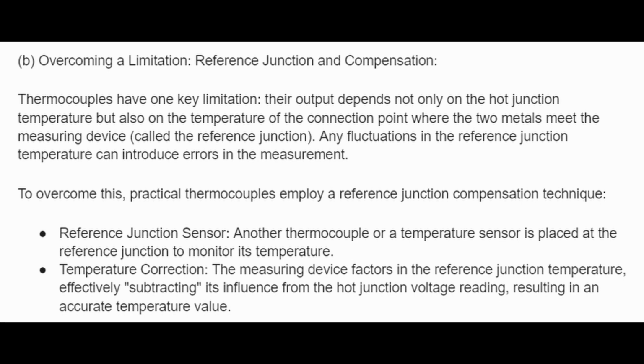Reference junction sensor. Another thermocouple or temperature sensor is placed at the reference junction for temperature correction. The measuring device factors in the reference junction temperature, effectively subtracting its influence from the hot junction voltage reading, resulting in an accurate temperature value.